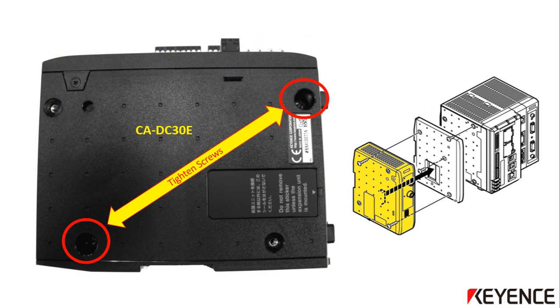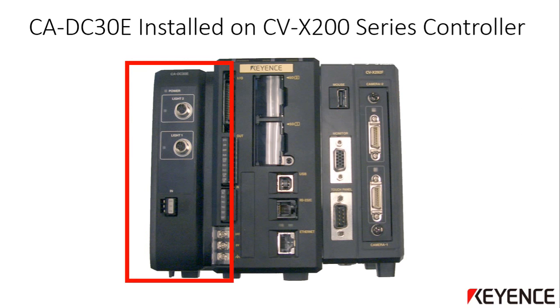You can now attach the CA-DC30E light controller to the CV-X200 main controller. Align the light controller with the spacer already mounted and tighten the two screws indicated here in red. If more than one light controller is going to be added, just repeat the same steps, installing the next light controller to the one already mounted. Be sure that the spacer unit that comes with each light controller is mounted in between each one as well. This picture shows the front view of the CV-X200 series controller with the CA-DC30E light controller properly mounted.